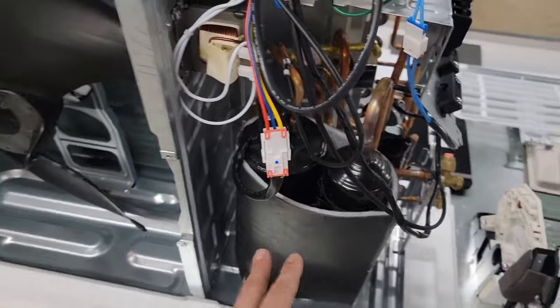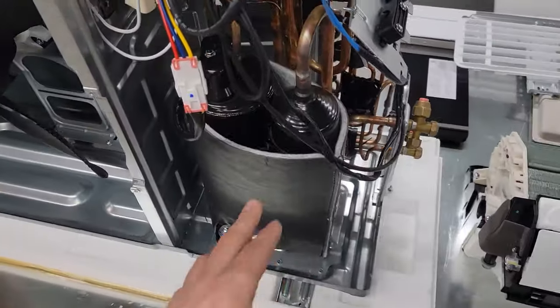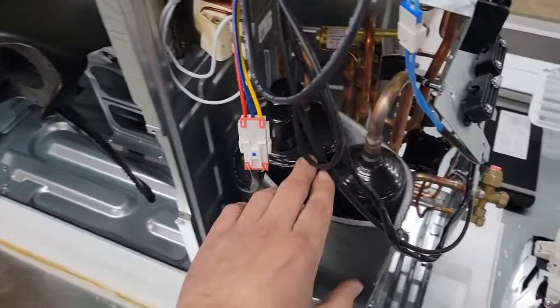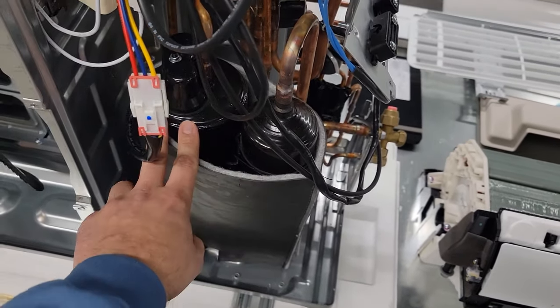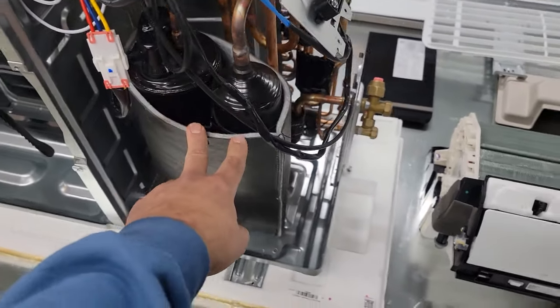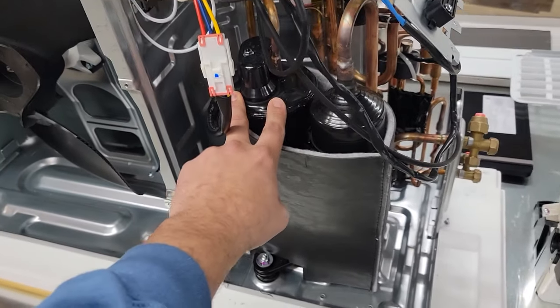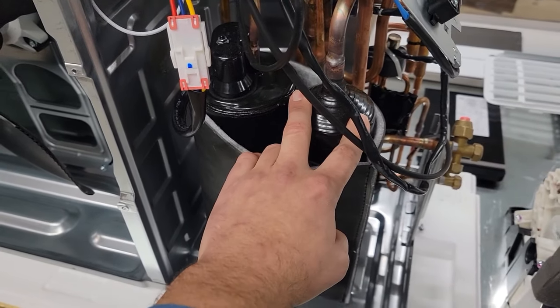Each motor is BLDC — brushless direct current. I'm going to explain how that all works and how this system operates. But first, let's go over the components. Now this is a sound blanket, and this is to deaden the sound of the compressor, although it's very small and it runs pretty quietly. This is a rotary compressor — an inverter rotary compressor. This right here is the accumulator, standard so that you don't have liquid flood back to the compressor.